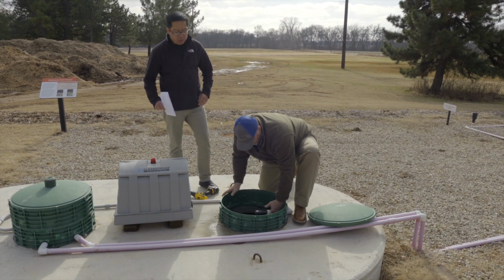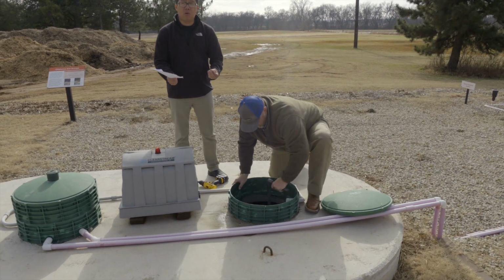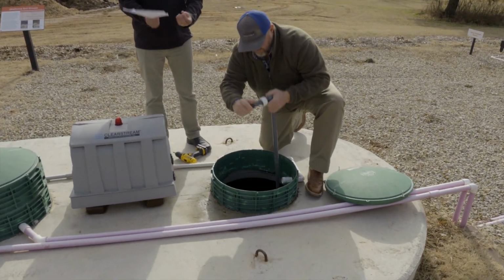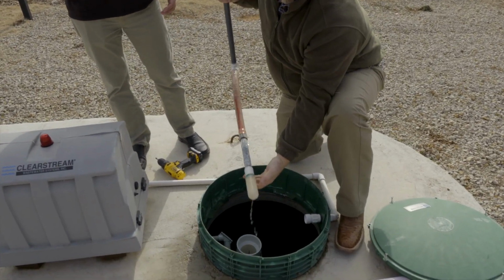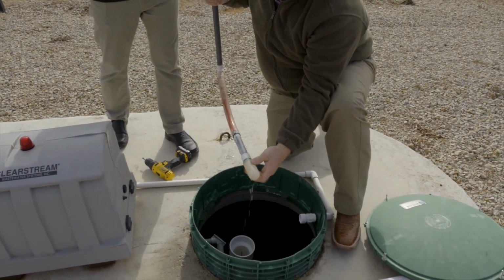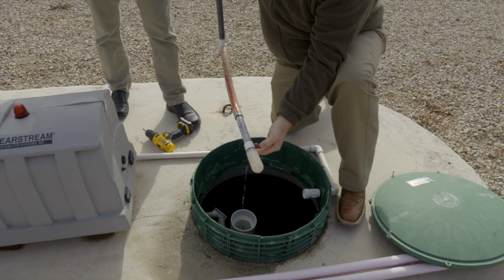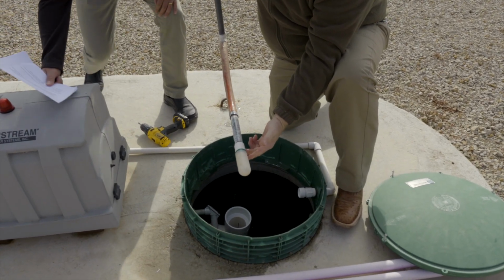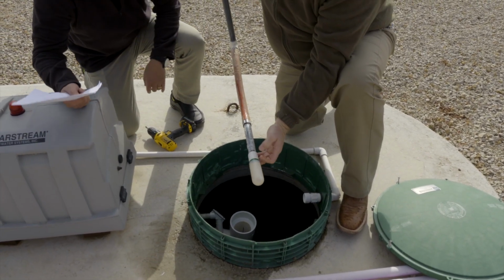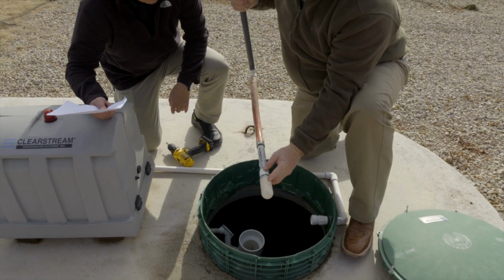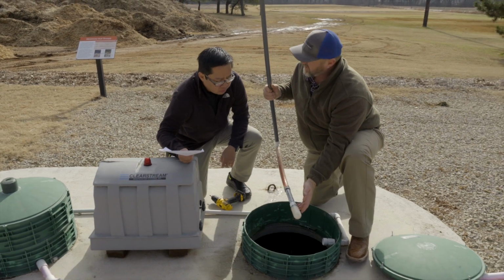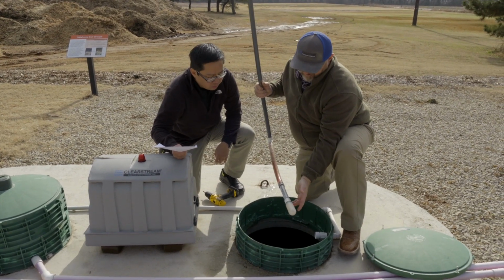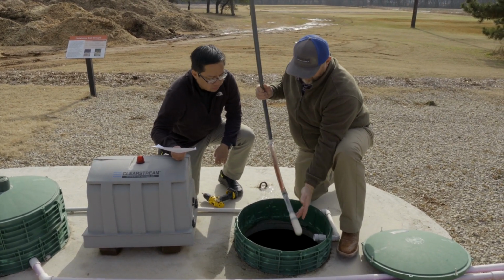And again, the diffuser spreads the air into the water, so you're aerating it, and when you aerate it, suddenly the microbes are happy because there's oxygen. You have to make sure that it's clean and not clogged in any way. It could have growth on it. It's best to replace it every 6 months to a year. Annually is a good time to replace the diffuser.